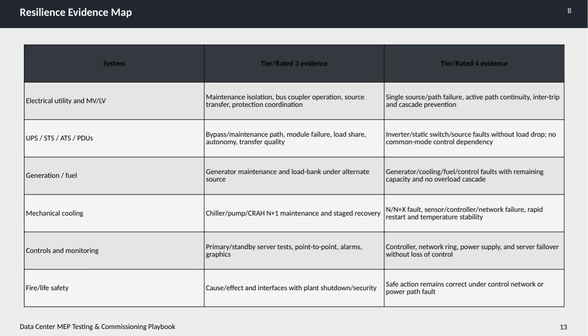Starting with electrical utility and MV/LV systems, Tier 3 focuses on maintenance isolation, bus coupler operation, source transfer, and protection coordination. For Tier 4, we see additional requirements like single source or path failure tolerance, maintaining active path continuity, and preventing intertrip and cascade failures. Moving on to UPS, STS, ATS, and PDUs, Tier 3 evidence includes bypass or maintenance paths, module failure handling, load sharing autonomy, and transfer quality. Tier 4 demands more stringent fault tolerance, such as inverter faults or source faults without any load drop, and no dependence on common mode control.